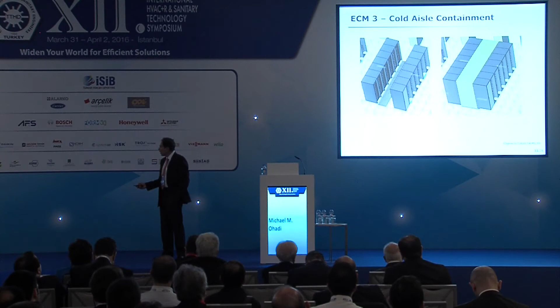Shown here schematically, the software demonstrates that if you do this, you substantially improve your temperatures. For this data center, the cost was $3,000, and the annual savings is $15,000, so the payback is about 3 months. Separation of hot and cold aisles is one of the easiest things you can do for quick savings.